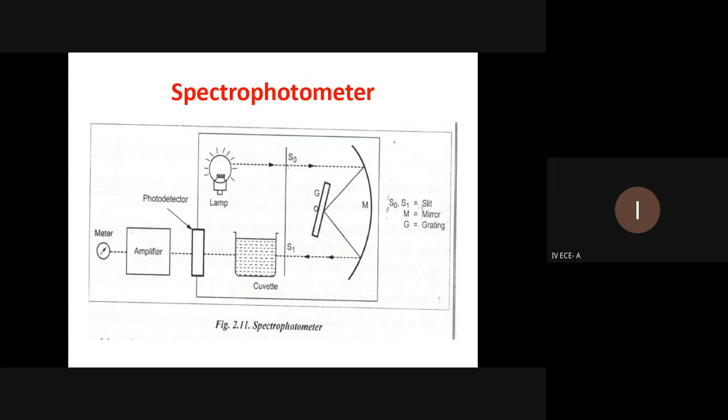If a single detector such as a photomultiplier tube or photodiode is used, the grating can be scanned stepwise so that the detector can measure the light intensity at each wavelength. Okay. An array of detectors such as charge coupled devices or photodiode arrays can be used. In such a system, the grating is fixed and the intensity of each wavelength of light is measured by a different detector in the array.